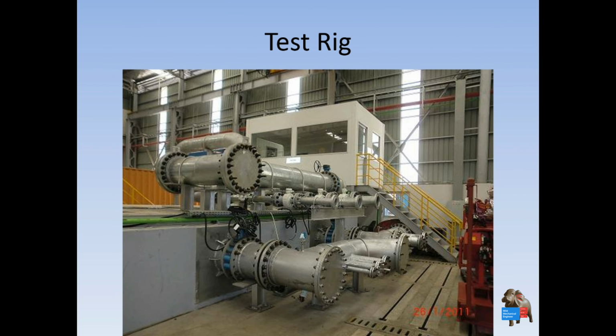Okay, this is typically a test rig for pumps. As you can see here, we have a big pipe in, and a small one. This depends on how big your pump suction is that you want to test. And this is a water reservoir. Actually, there is very deep water inside, at least 4 meters, and the volume of it, of course, depends on your test rig design, at what cubic meters per hour you can test in your test rig. You define it based on your need actually.